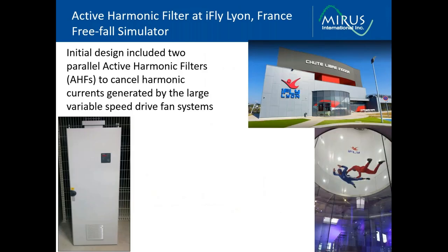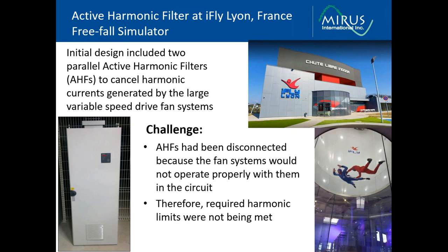Another parallel active filter installation that did not go well was one applied to a skydiving simulator in Lyon, France. Initially, they used two active harmonic filters to treat the harmonics generated by the fan systems used for these skydiving simulators. The AHFs had been disconnected because they couldn't get the fan systems to work properly, again due to the high frequency noise introduced by the AHFs. With the AHFs disconnected, the required harmonic limits were not being met.